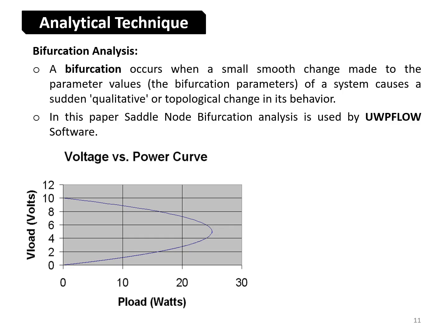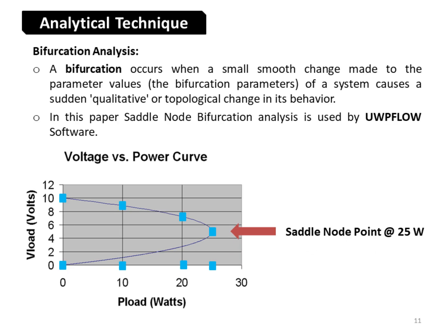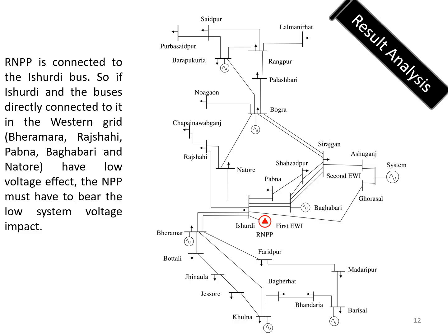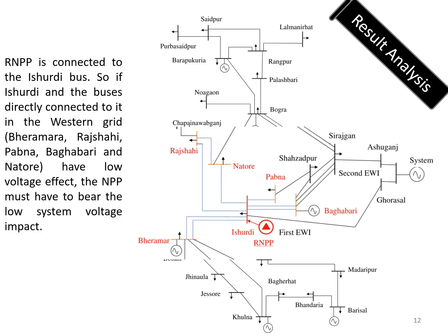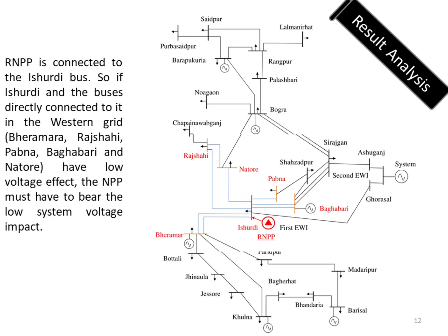We used bifurcation analysis, specifically saddle node bifurcation, via UWPFLOW software. This method helps identify voltage collapse points as load increases. The graph illustrates the voltage power curve, with the saddle node indicating the stability limit. Rooppur NPP is connected to the Ishurdi bus. Therefore, if Ishurdi and neighboring buses like Bheramara, Rajshahi, Pabna, Baghabari, and Natore experience low voltage, the NPP will also be affected. This makes voltage monitoring in these areas critical.